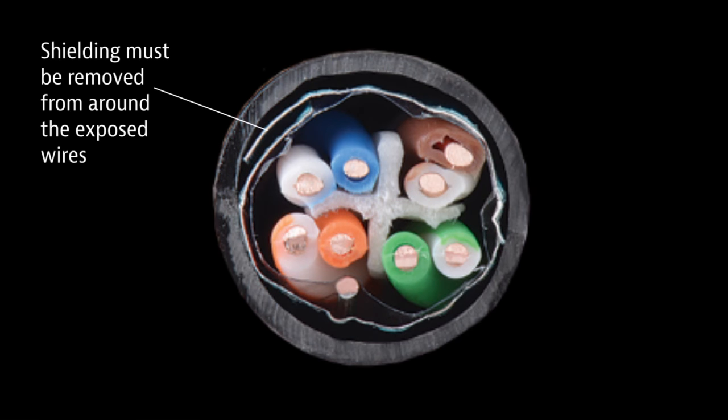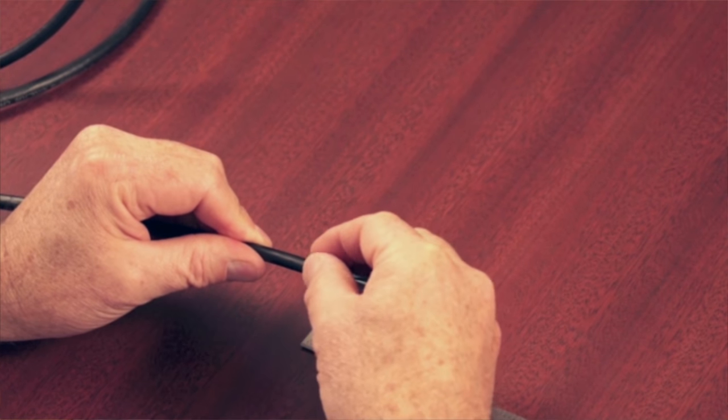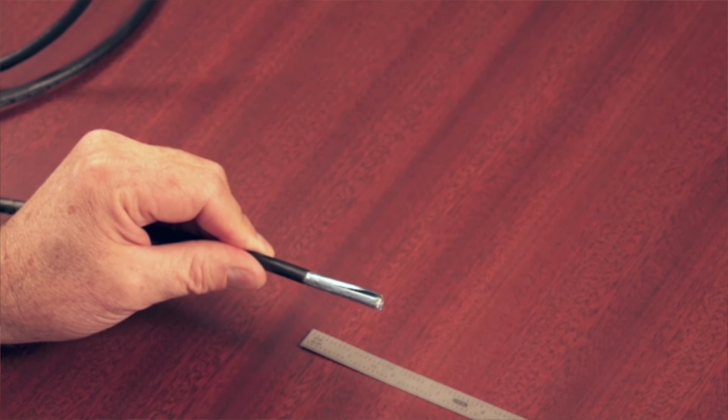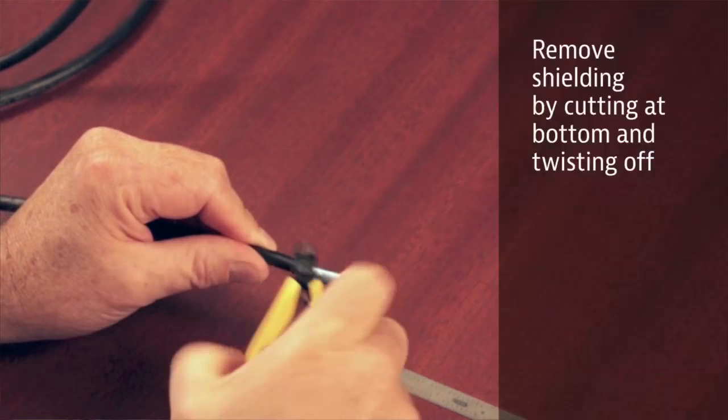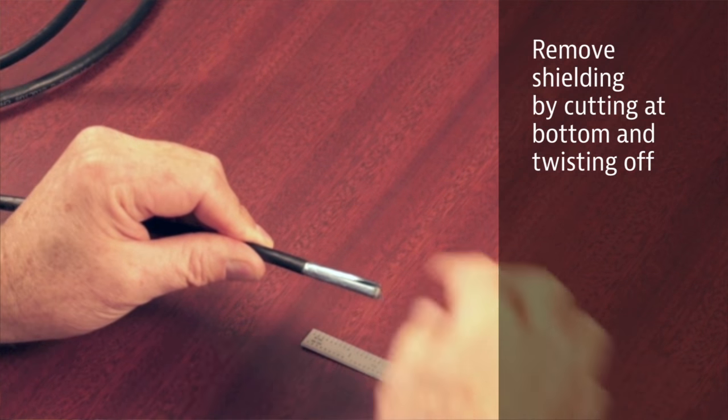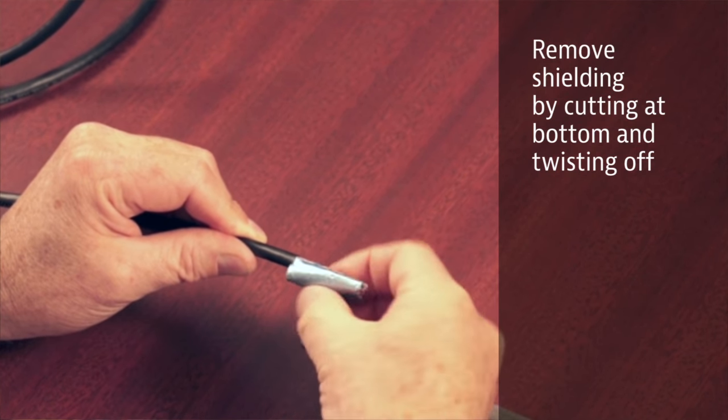Sometimes the shield will come off with your slug, sometimes it won't. If it does not come off, you want to go ahead and peel that shield off. One issue with the shield on these cables is it is very heavy and can slice your fingers. You want to be careful. Score the shield down by the jacket, or take a pair of diagonal cutters and nip the shield. Peel this off and discard the shield.